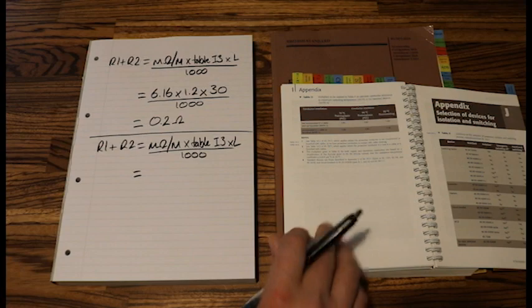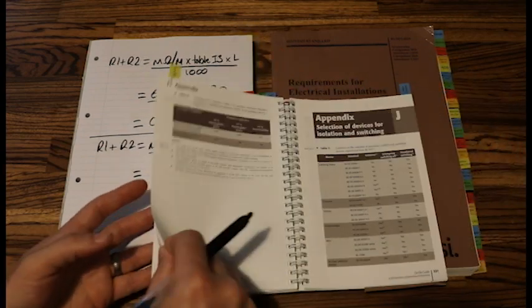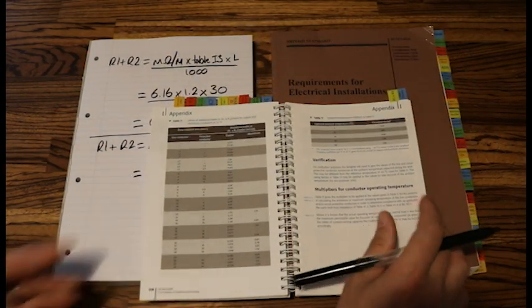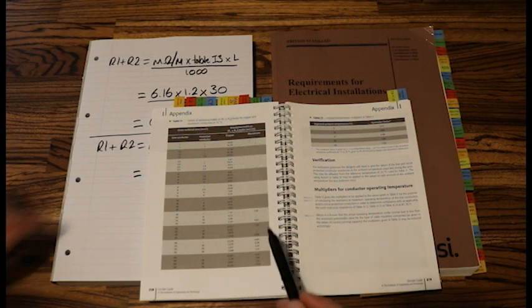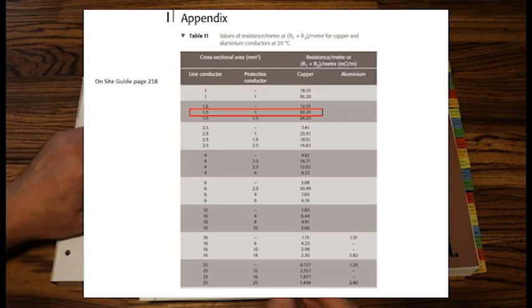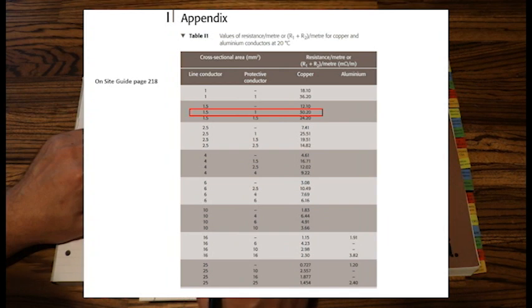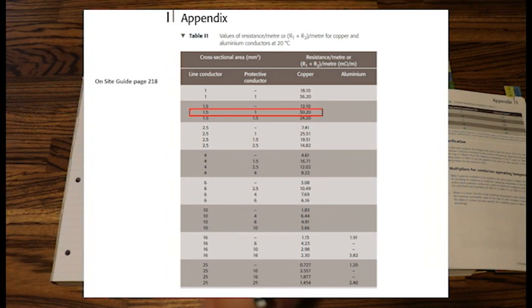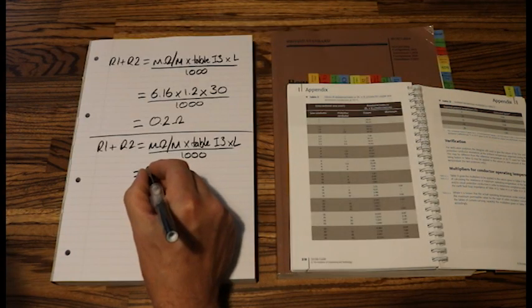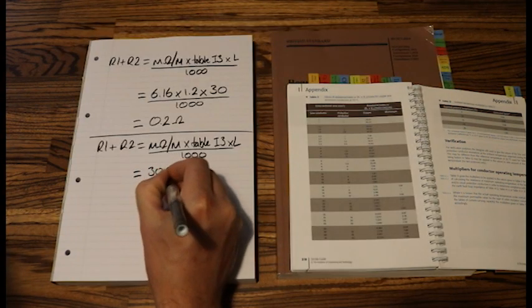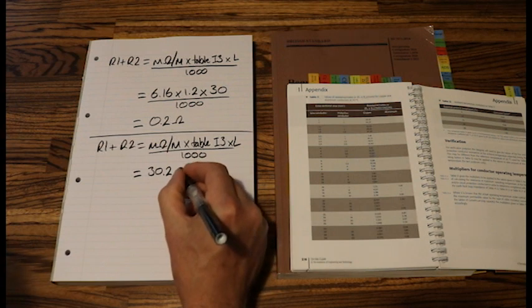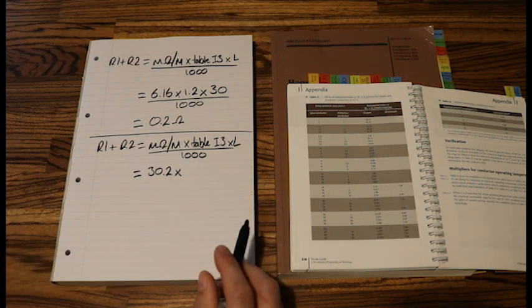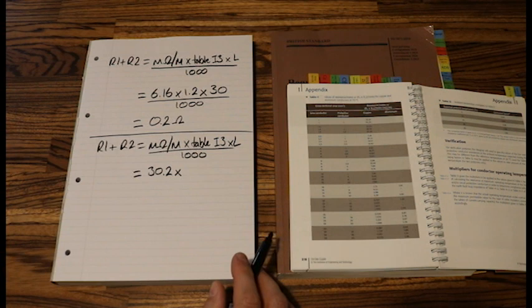Now let's have a look at our table. So we've got 1.5 mil live and 1 mil earth. So my milliohm per meter value is 30.20. 30.20. Let's put that 30.20.